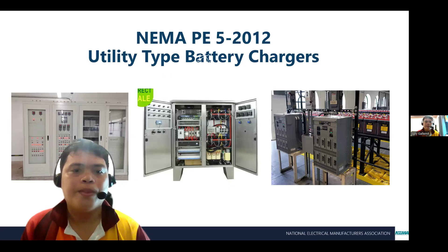The standard covers chargers, charger types, output rating, voltage regulation, ripple limits, overload protection, alarm functions, grounding requirements, and environmental operating conditions. It also includes guidelines for testing charger efficiency and stability, temperature rise, insulation performance, and long-term durability. So, example sa NEMA PE5-2012 utility battery chargers is muna siya.